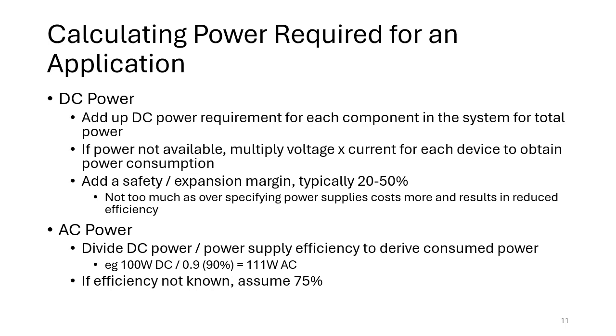So we've got a 100 watt power supply. If we assume 90% efficiency, then we take that DC power and divide it by 0.9, and that would give us an AC input of 111 watts. And then we probably need to add a bit of safety margin on that as well. AC power is less important, but it can be useful if whoever's supplying the power wants to know how much power you're going to be consuming. So that's how we calculate the AC input power. And of course, you'll also need that to check fuses and so on.